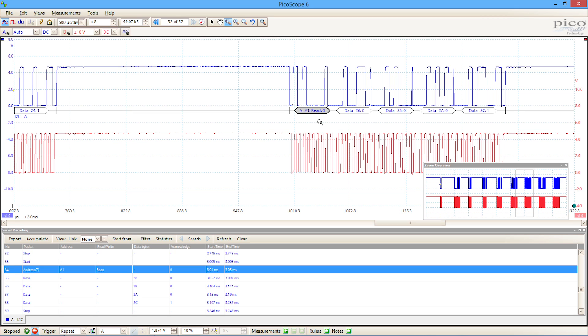It also highlights that same packet on the upper time domain screen here so that we can see exactly the correlation of the data display, the timing display, the waveform characteristics at that point, so that we can search for any signal integrity errors that are affecting the performance of the device under test.